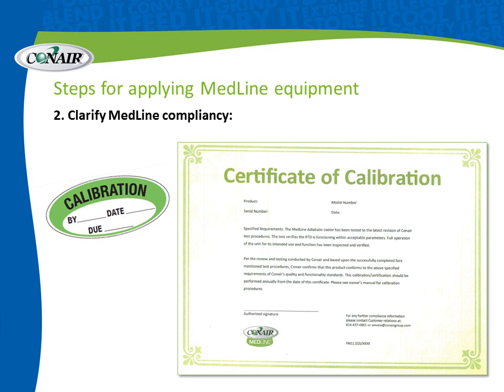And here are some pictures of those calibration documents. The sticker on the left that is placed right on the equipment shows who calibrated it, when, and when it will be due again. All very important for medical compliancy. And along with that comes a certificate of calibration signed by the individual that did that. Now this calibration certificate, a copy of that, is actually kept in the files at Conair that can be retrieved at any time for any customer that has a piece of MedLine equipment.